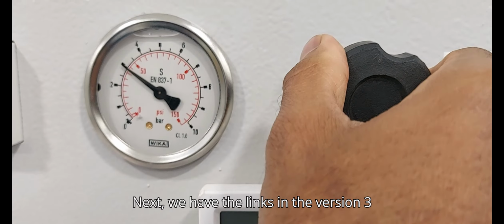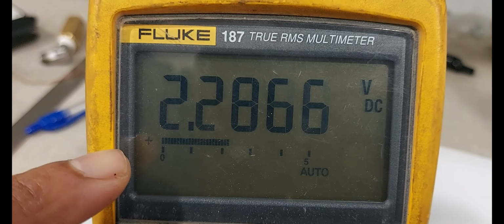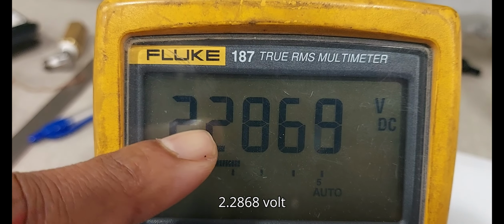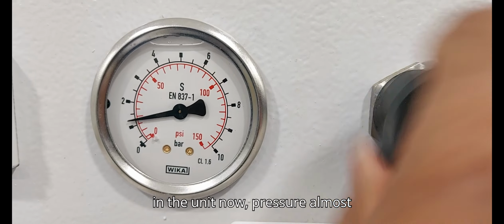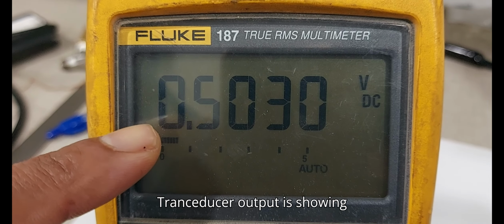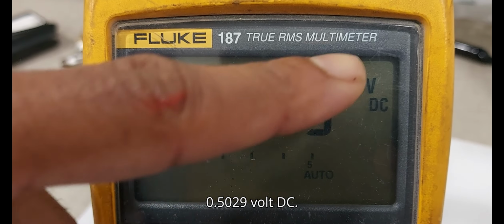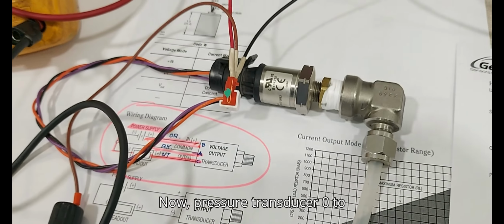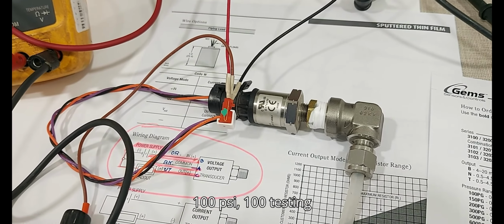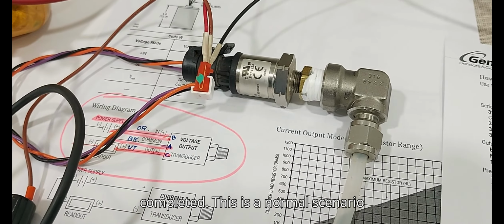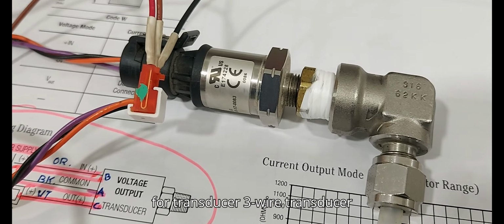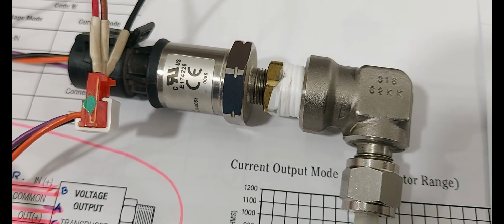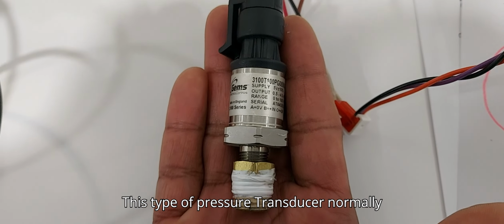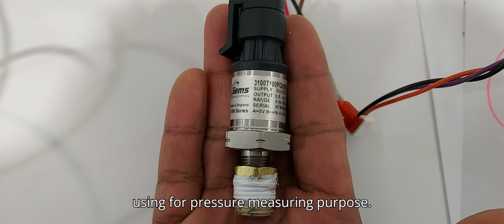Next we are releasing the pressure to 3 bar. Okay, 3 bar. Transmitter output is showing 2.2868 volt DC. Next we are releasing all pressure in the unit. Now pressure almost released. Transducer output is showing 0.5029 volt DC. Now pressure transducer 0 to 100 psi functional test completed. This is a normal scenario for 3-wire transducer testing. This type of pressure transducer is normally used for pressure measuring purposes.